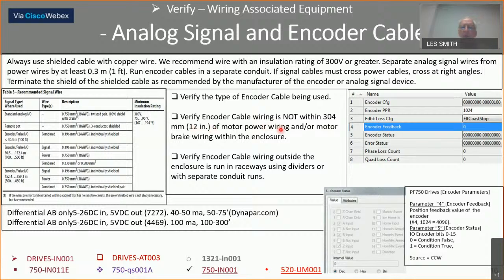Something like that might appear on the quiz. Verify the encoder cable outside of the enclosure is run in raceways using dividers and/or separate conduit runs on that. I put this up over here. The encoder feedback, if it's a quadrature, you're going to get 4096 pulses for a 1024 encoder.